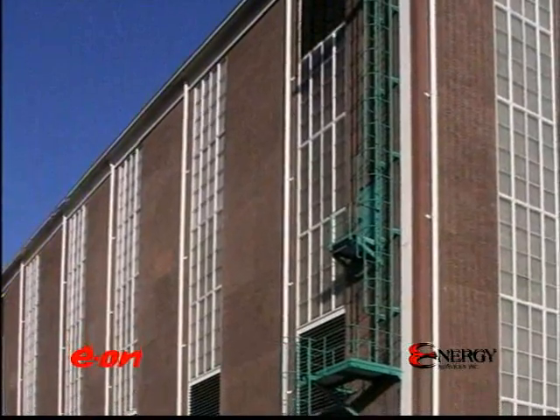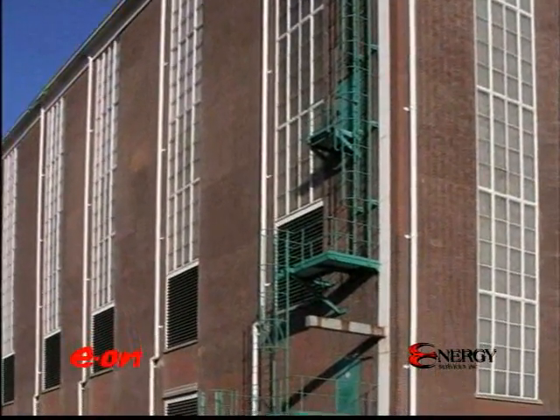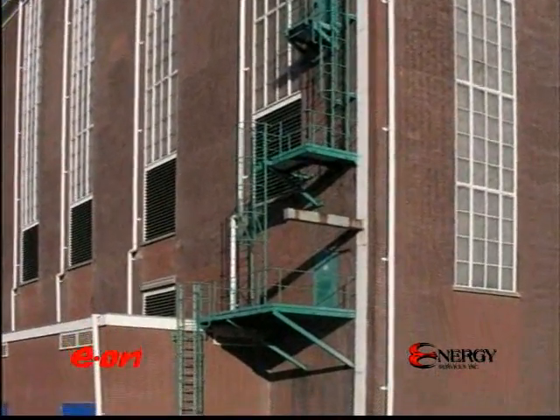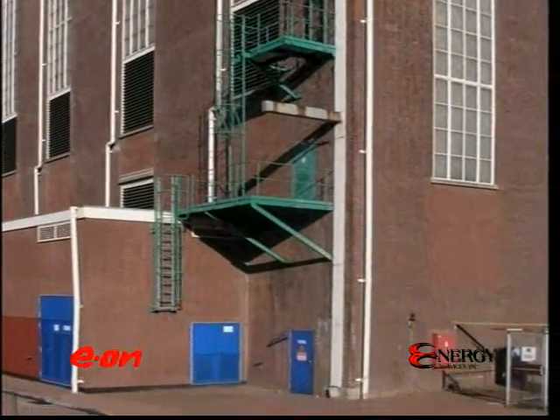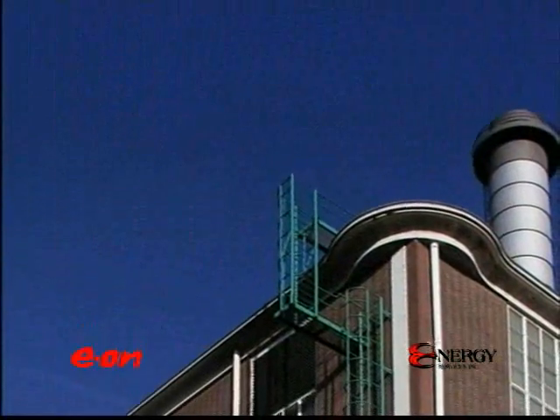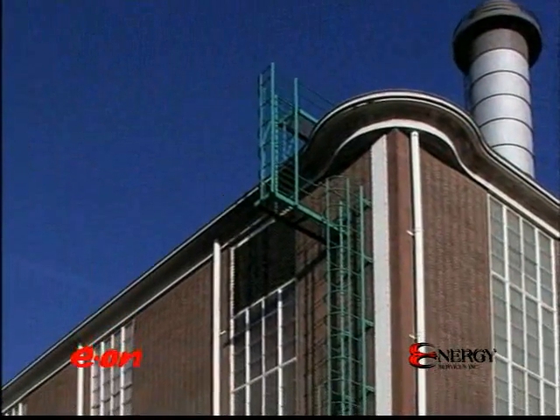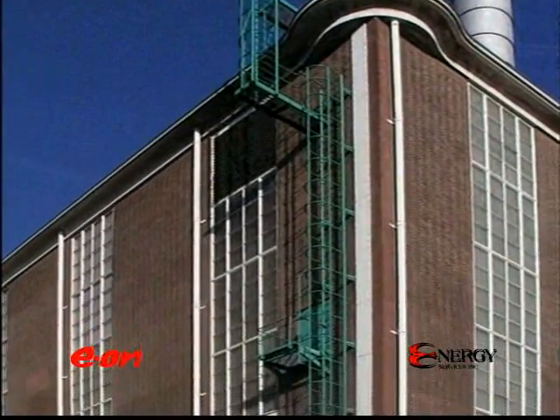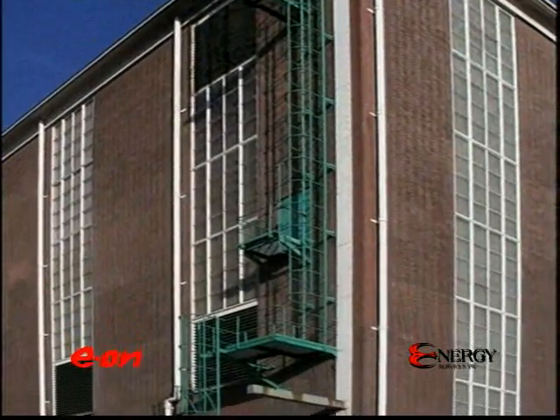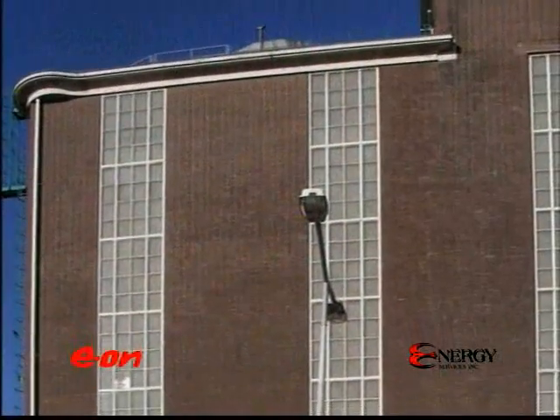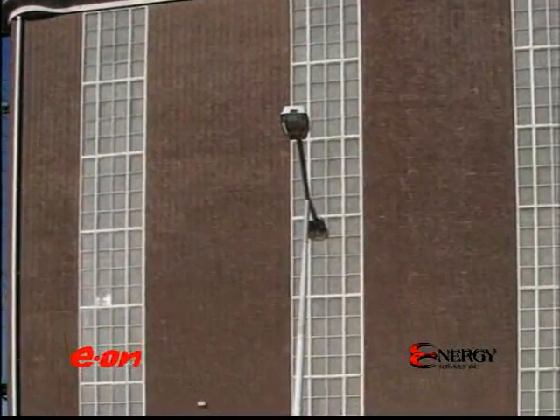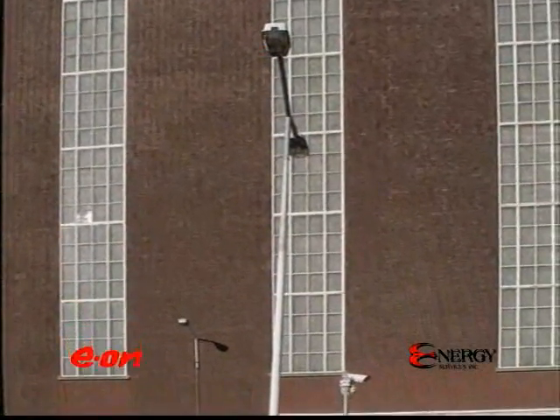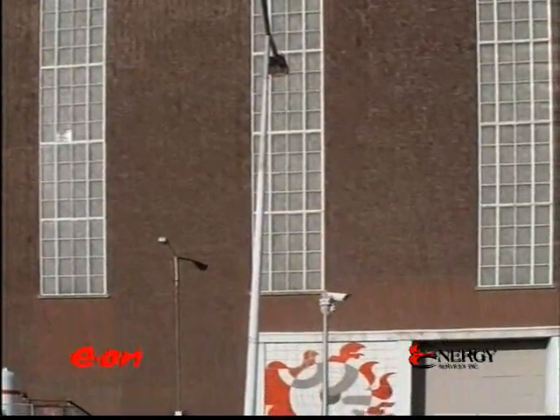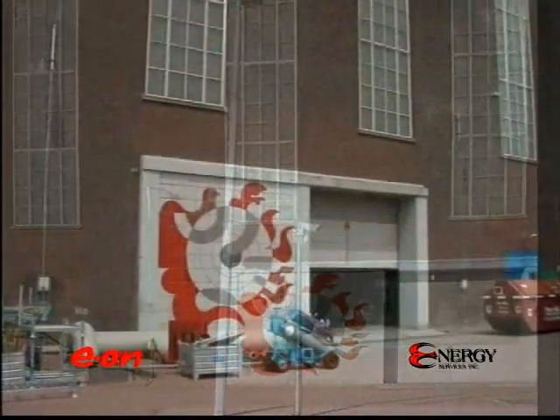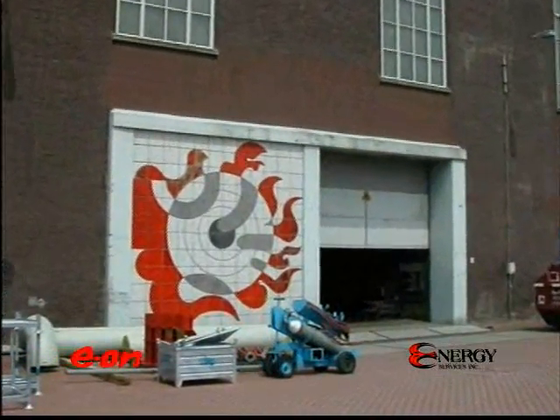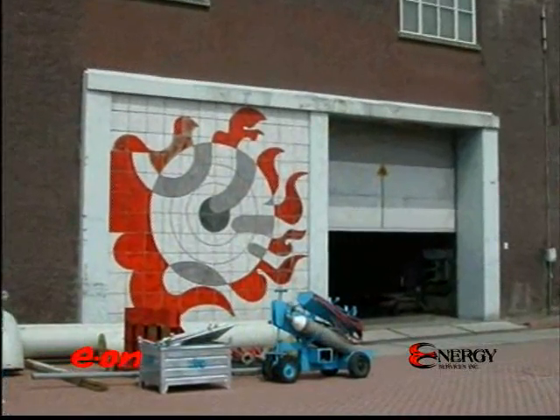These gas turbines were reaching the end of their useful lives, and E.ON desired to replace them with new units that would provide the utility, dependability, and economy of state-of-the-art equipment. ESI undertook the task of fulfilling these desires and proposed a system utilizing a single 100-megawatt generator driven by a pair of GE LM6000 DLE gas turbines and reusing the existing exhaust heat recovery boilers. Let's take a look at how this functionally elegant and cost-effective solution was accomplished.